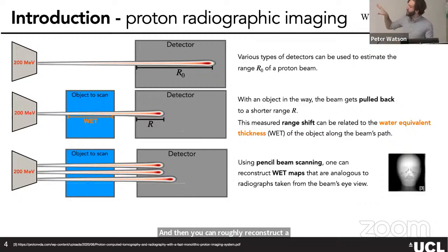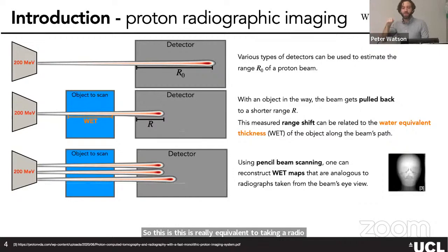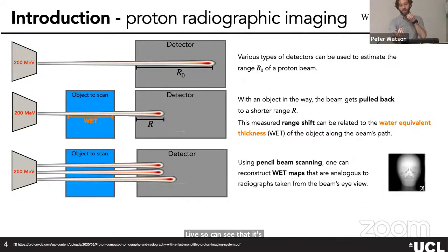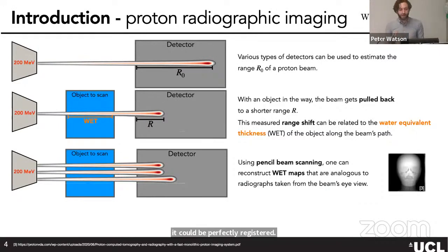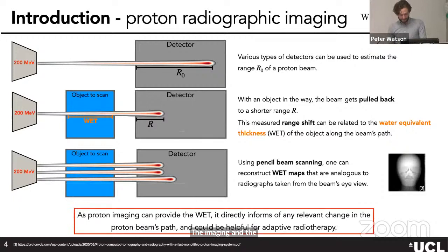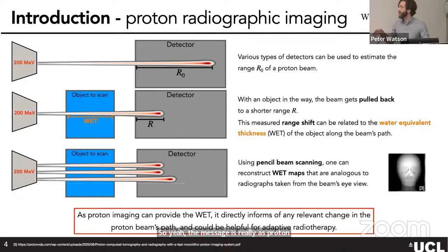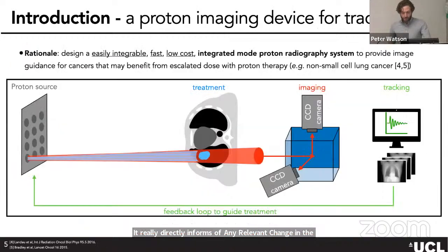To do imaging from this idea, you use a pencil beam scanning setup — instead of shooting one beam, you shoot many beams at different X-Y positions sequentially. You get an estimate of the WET at each point the beam enters the patient, and you can reconstruct a coarse WET map. This is equivalent to taking a radiograph of your patient with protons from the beam side, perfectly registered to the treatment.